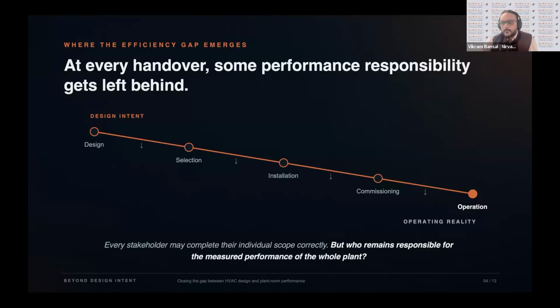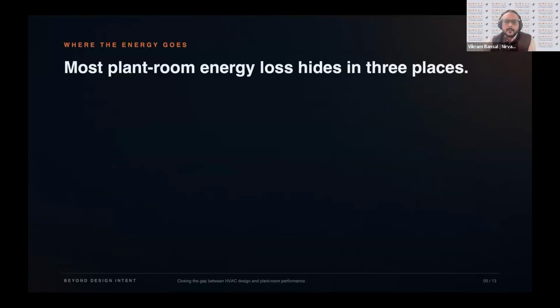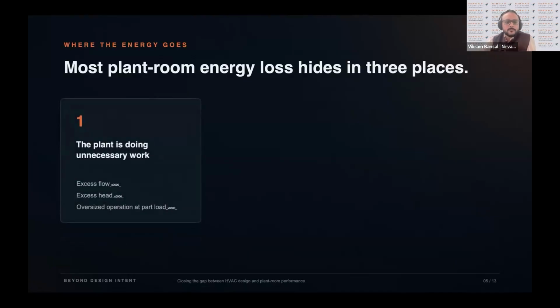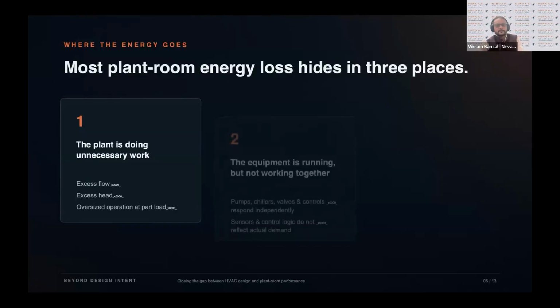So where can we find the leakages every plant room is having? I found that in the plant room there are majorly three places where these energy losses are happening. First, the plant room is doing unnecessary work. There is excessive flow from the design, excessive head from the design, and oversized operations at part load, because in northern India our buildings operate mostly at part loads, but because of missing controls they are either running in manual modes or running at an oversized condition.